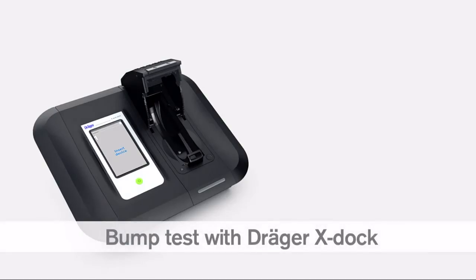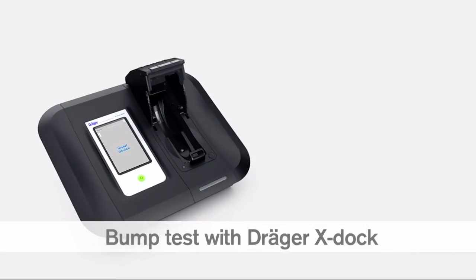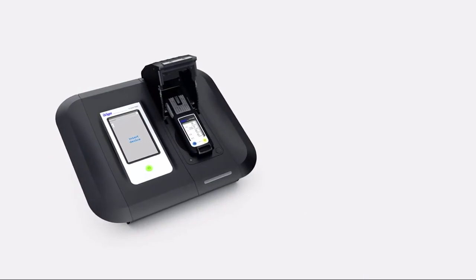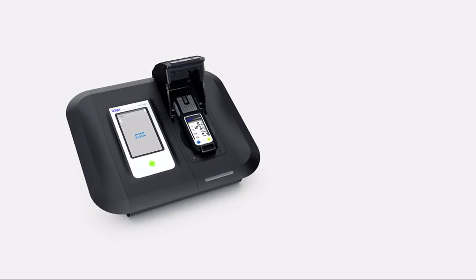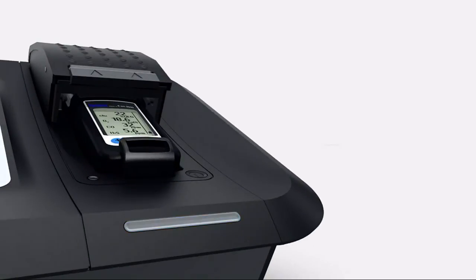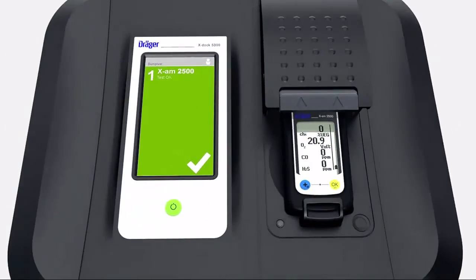You can also carry out a bump test with the Dräger X-dock station. Place an instrument inside the module. When you do so for the very first time, the Dräger X-dock recognizes the device and logs it in its integrated database. The LED strip flashes blue. When the LED changes to green, the test has been completely successful. The X-Doc screen also turns green. Touch it to obtain additional information on the test results.